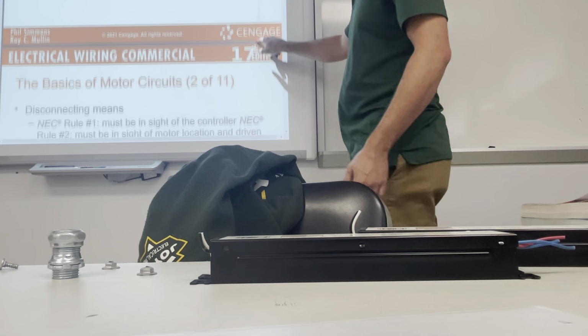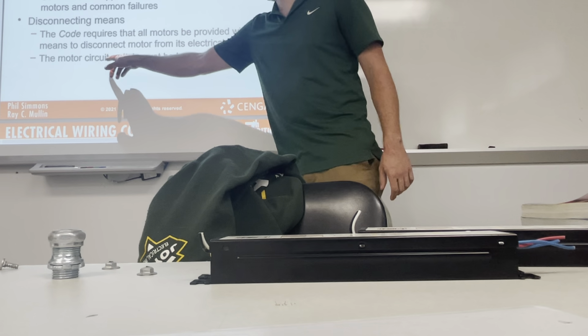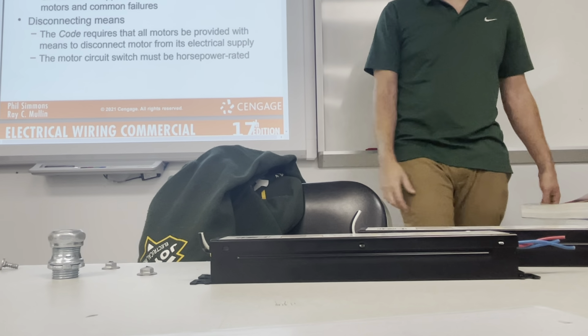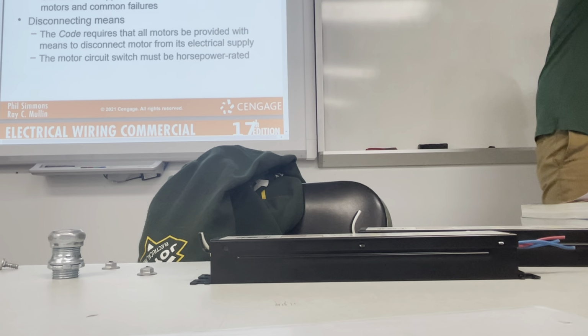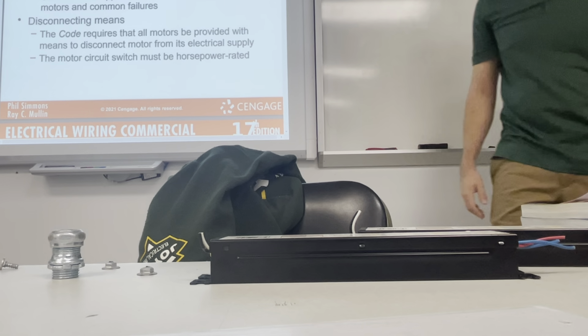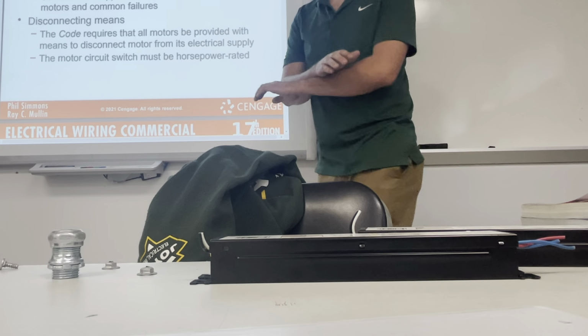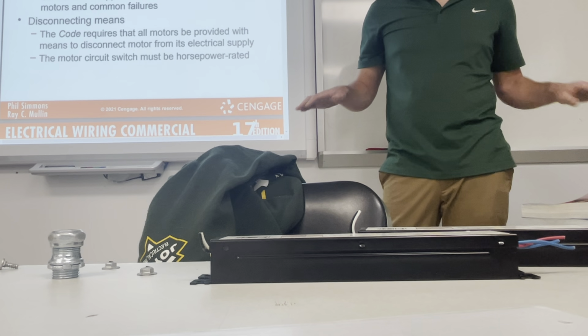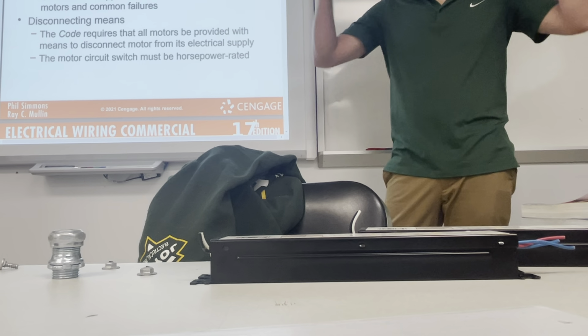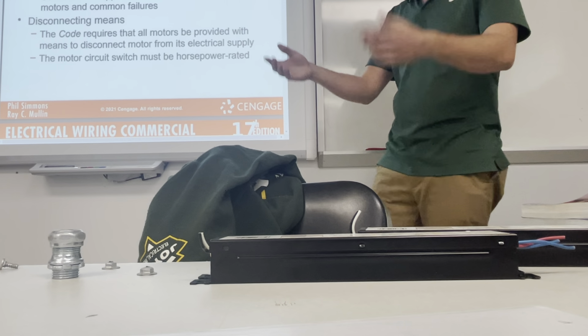And when we're talking about here, let's back up one slide. The motor circuit switch must be horsepower rated. We don't go by amps anymore when we're dealing with motor control. It goes by horsepower rating, okay? Once again, I am not going to get into all the nitty gritties. There's too much here to talk about. Just so you know some blanket information, so you know what you're looking for when you get into motor control next semester.